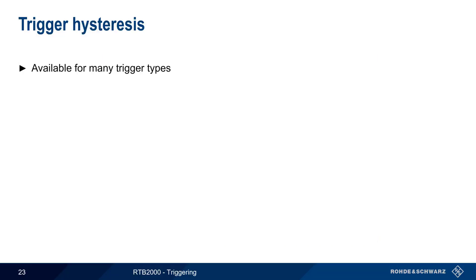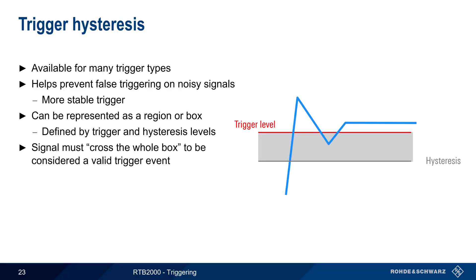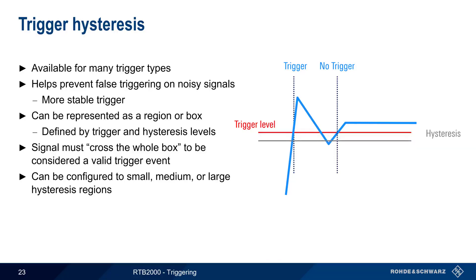Trigger hysteresis is available for many trigger types. Hysteresis is used to prevent false triggering on noisy signals and provide a more stable trigger. Hysteresis can be represented as a region or box that's defined by the trigger and hysteresis levels. In order to be considered a valid trigger, the signal must cross the whole box in one direction. In this example, the first crossing of the trigger level is a valid trigger event, but the second crossing is not. On the RTB, hysteresis can be configured as small, medium, or large regions. If we changed our region in this example to small, the second trigger crossing now becomes a valid trigger event.